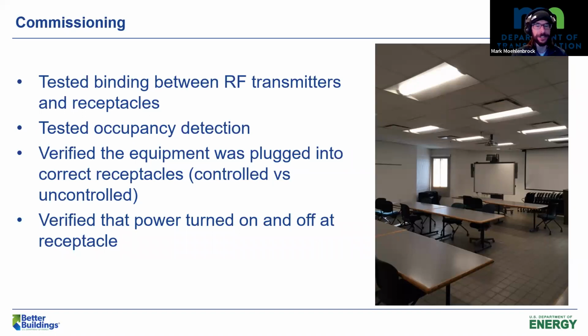But to test the occupancy detection, I basically ran extension cords to some fans and lights and things like that, and walked into the room. And when it came on, I knew it was turning on properly, and then I had to leave the occupancy zone. And that's why I had the extension cords. So I could kind of peer into the room, and if the fan turned off in 10 minutes, I knew it was working properly. So there might be a more sophisticated way to do it, but I was kind of just trying to make it work. And then the big part of it was making sure that the proper equipment was plugged into the correct receptacles. So there were a couple of refrigerators I was a little bit nervous about, but we made sure it was plugged in correctly. So next slide, please.